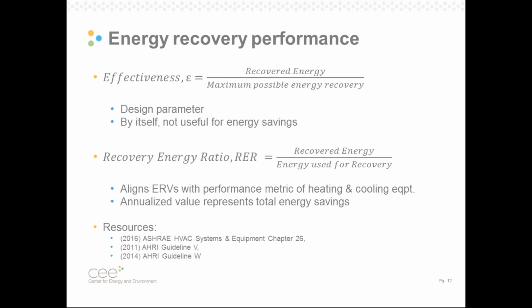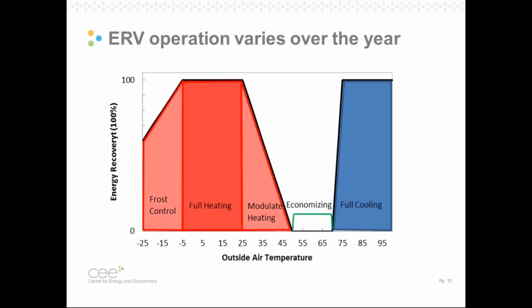And this is really useful because it aligns the performance of ERVs in the same units as the metrics we use for defining heating and cooling equipment performance, for example, EER or efficiency. And an annualized value of RER gets at the total energy savings potential of our ERV technology. Just want to say here that there's a ton of technical resources about air-to-air exhaust energy recovery systems. ASHRAE, AHRI, they have great information. You can learn more from that documentation than I could possibly convey to you today. So from a technical perspective, it's all out there.